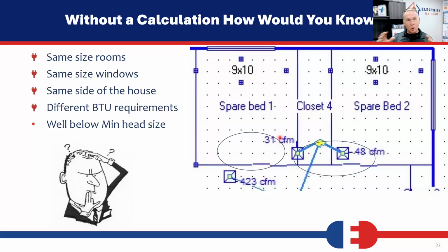which means if CFMs are going to correlate with the BTUs that we need to deliver, why do I need more conditioning in this room than I need in this room? I'll give you a second to ponder that. This room has 2 outside walls, and the reason I bring this to you this way is when we do our classes and we have guys from the trade in there, a lot of them can't put this together.